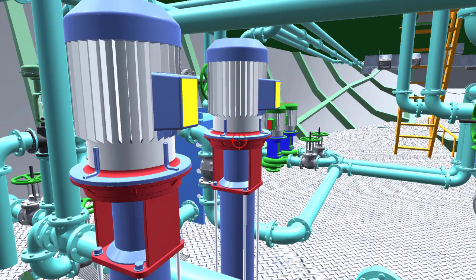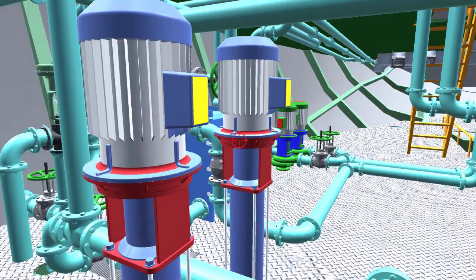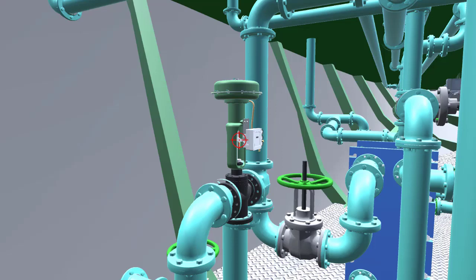Such as the condenser for the boilers, for the feed water tank, and also it supplies for the fresh water generators, for the coolers of the lubrication of the main engine, and also for the air cooler of the main engine, and so many other things. The seawater system is in duplex with the centralized cooling system, which is the fresh water cooling system.